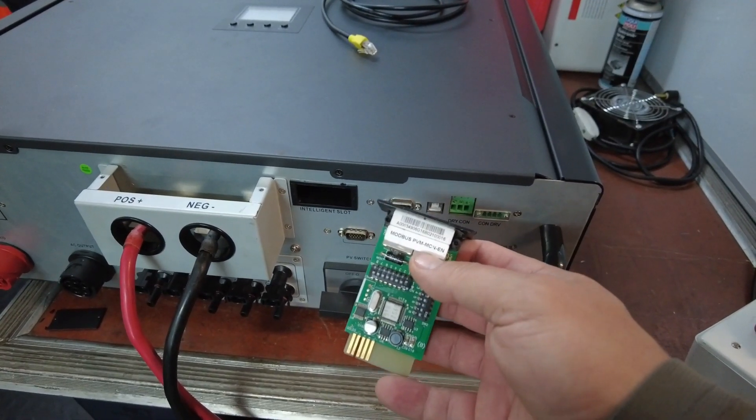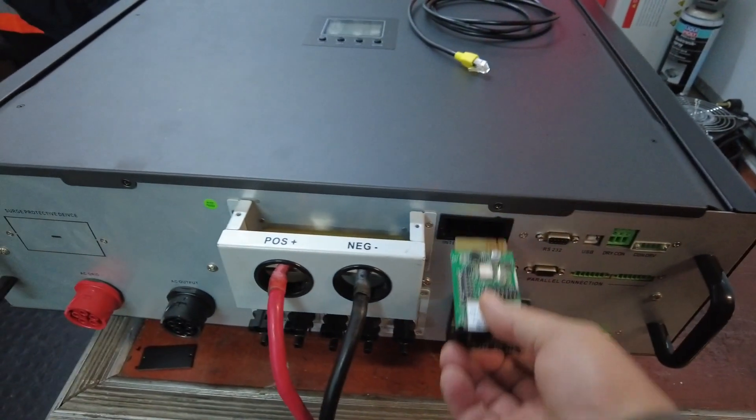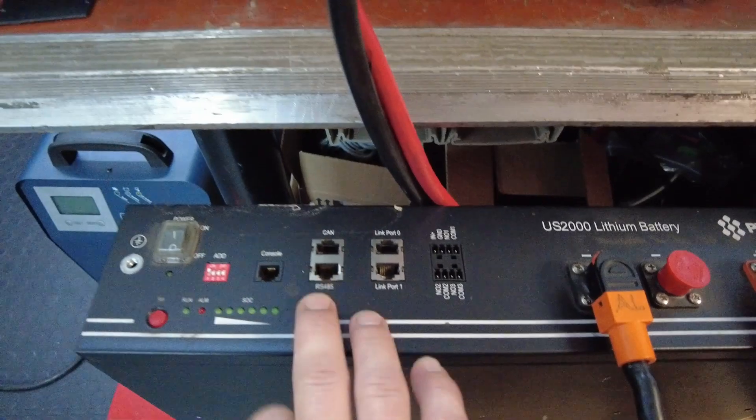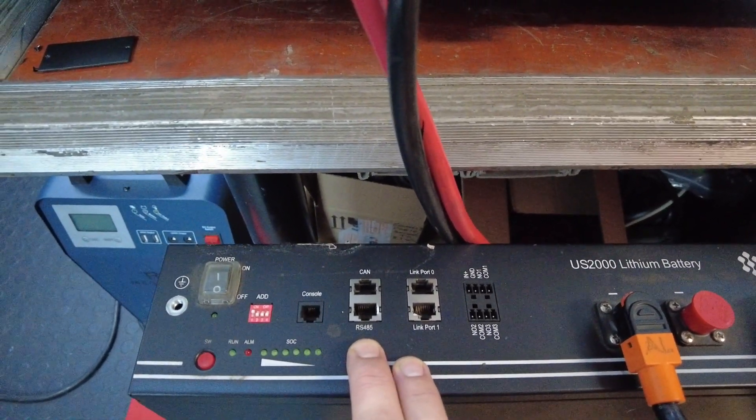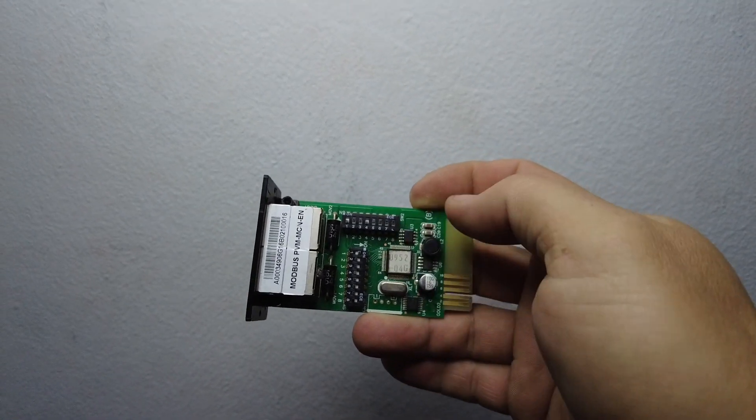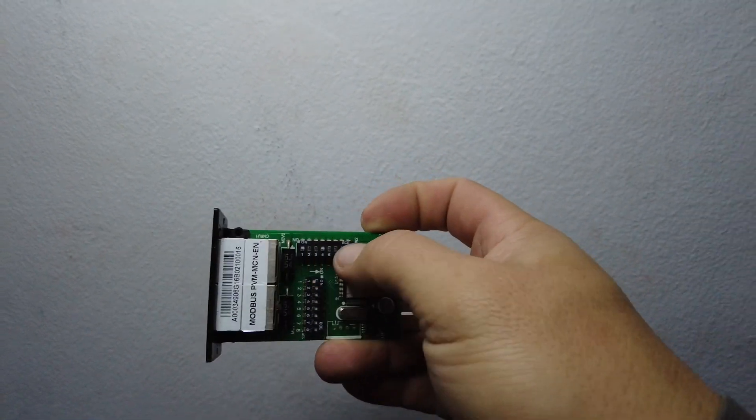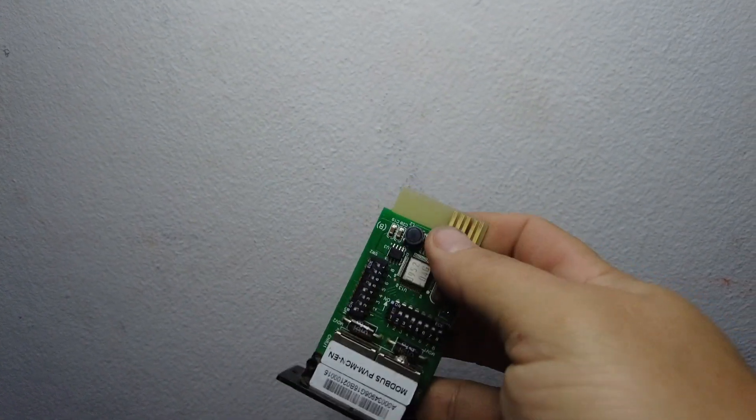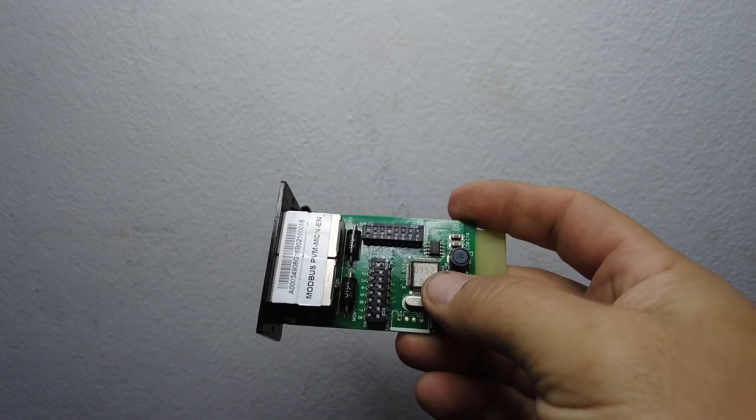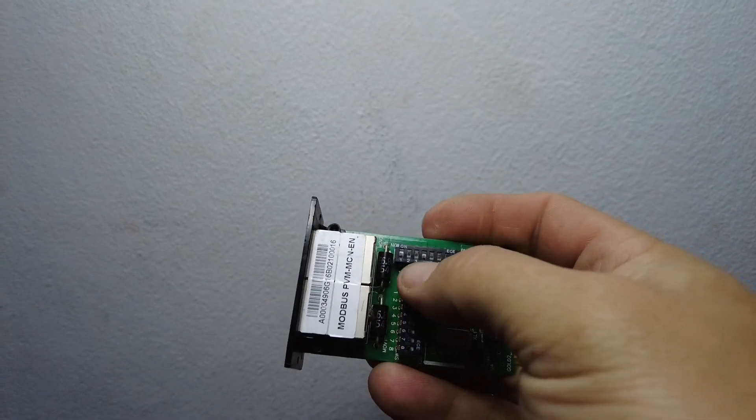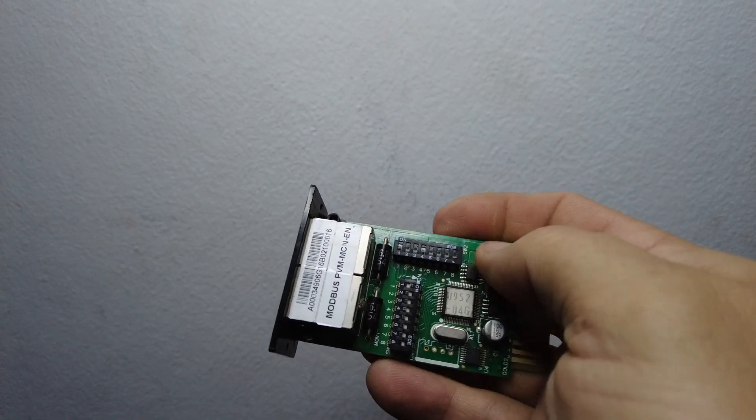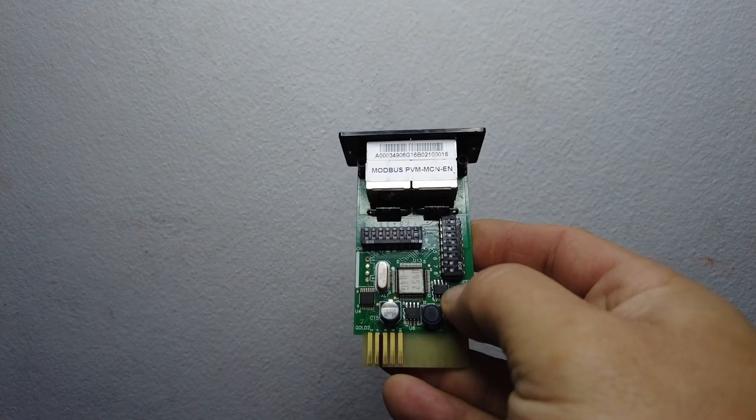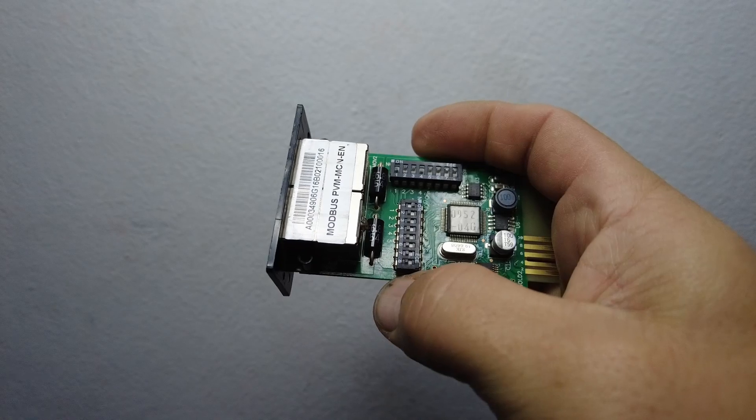Referring to that intelligent slot, you need to get your hands on one of these Modbus cards which will slot in there, providing you with your RS-485 protocol which will assist you in communicating with the battery's RS-485. Generally when you remove the Modbus card from the packaging, your dip switches should be set correctly already. However, let's just cover it. This is your switch number two as you can see, labeled on the PC board, and this is switch number one.